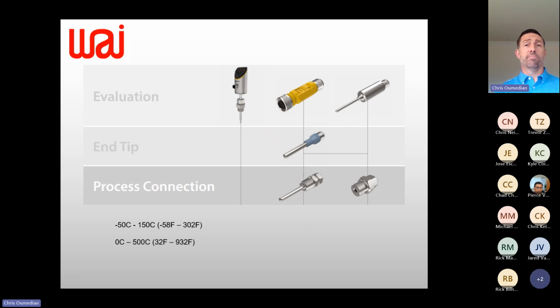We do offer plain RTDs if people want to use a puck or they have an interpretation card in their PLC or IO block. We can offer RTDs. Our solution, which we find a lot of people love, is to not take that traditional RTD with that weird low-level signal where they have to buy a special card for their PLC or their IO rack, but to take care of that conditioning within the device and just give you a 4 to 20 milliamp output or a 0 to 10 volt output.